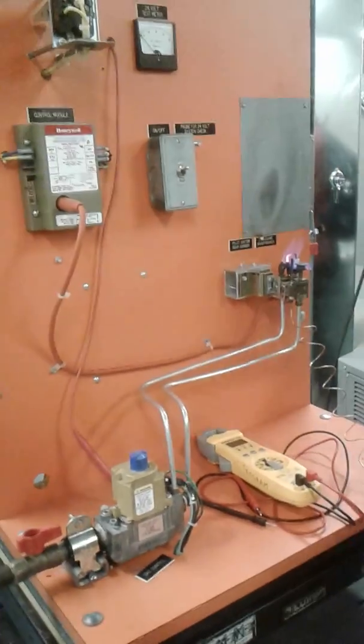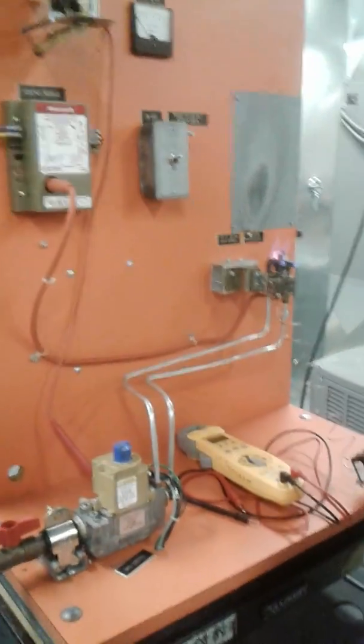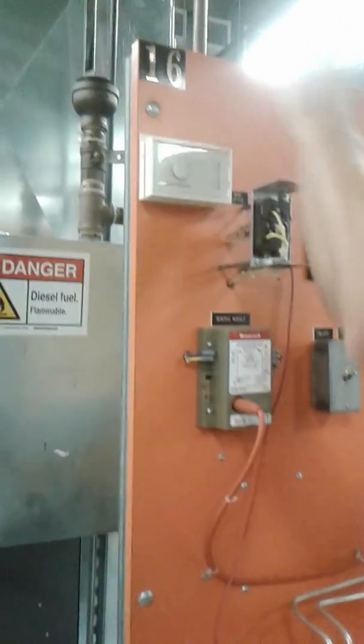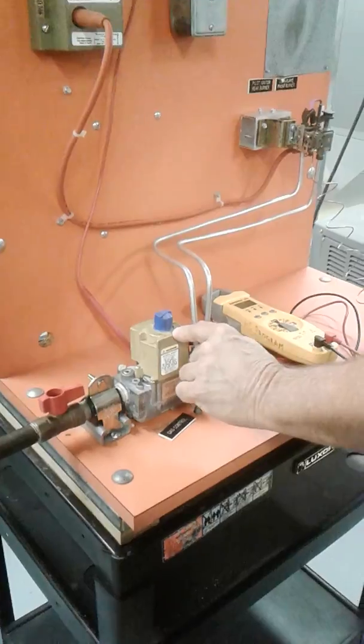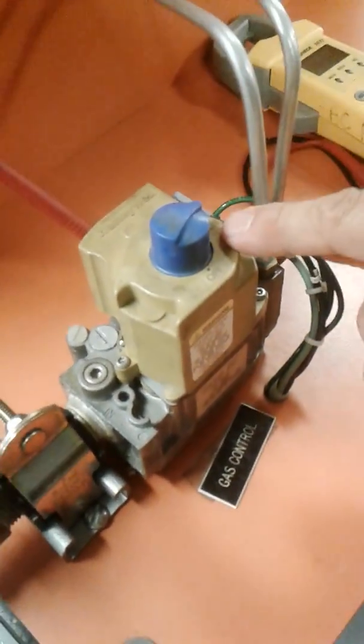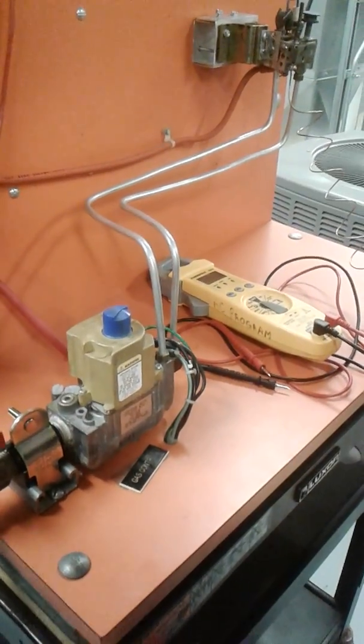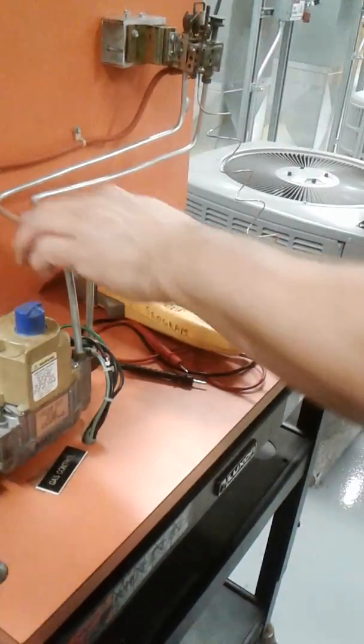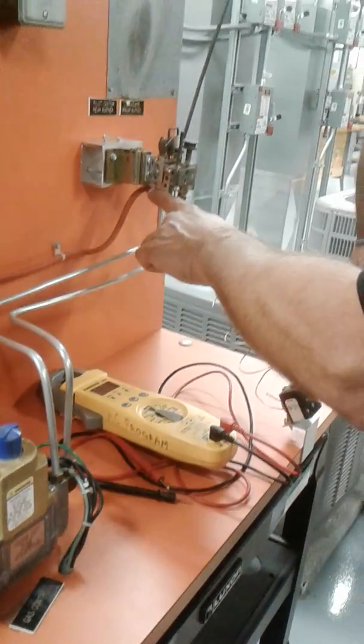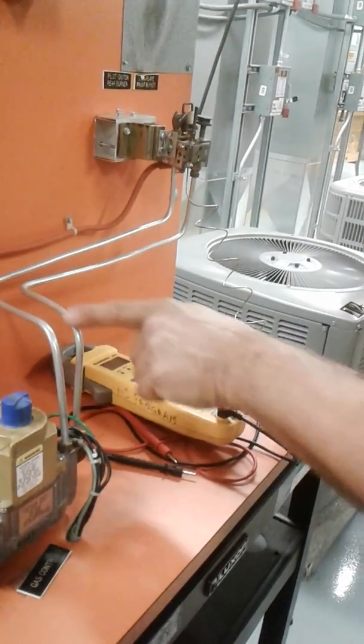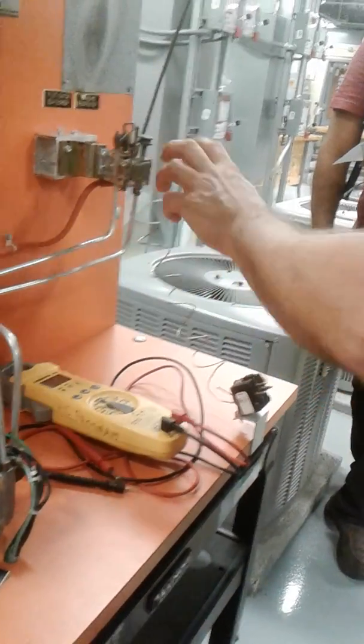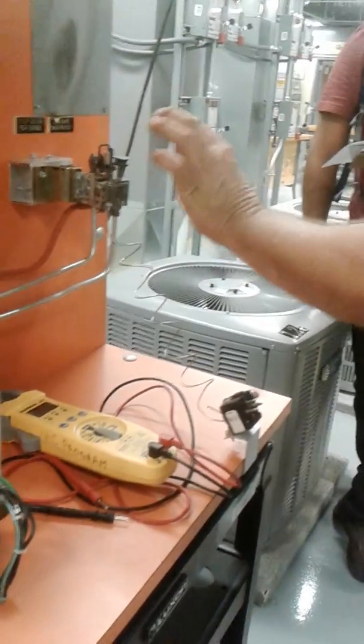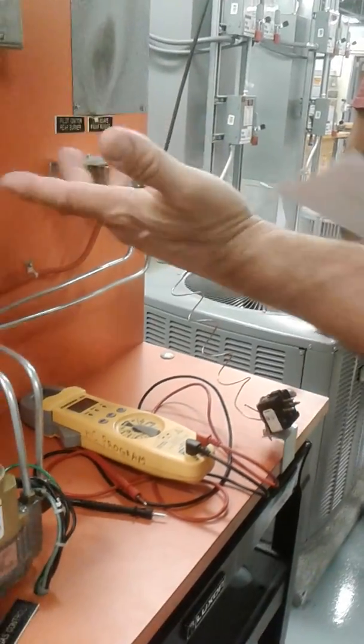Now, when all the switches are in the upright position, it runs normally. Check it out. Our power is turned on, our gas is on, our gas valve is on. Number one thing that people forget to do with this is turn the gas valve on. Off, on. Now, this is the gas for the spark igniter. This is actually our burner. This would be like the in-shot burners, but we just have a little Bunsen burner, as you would see in the science lab.